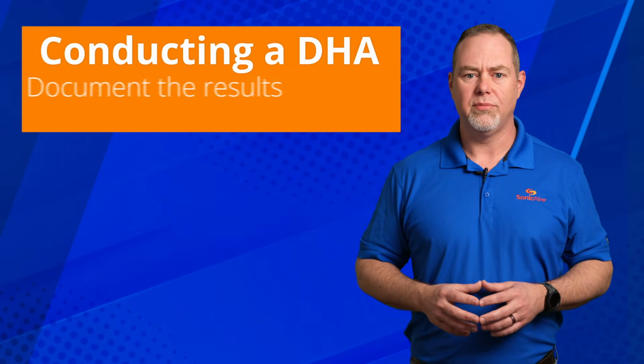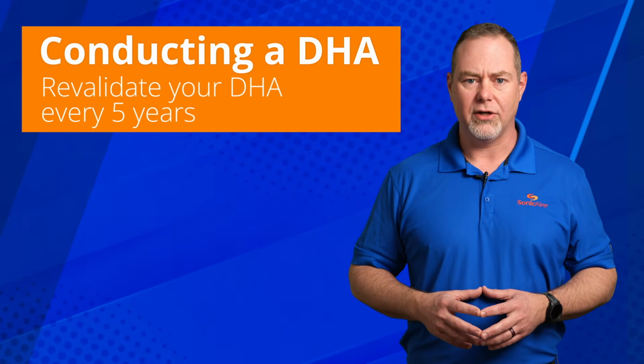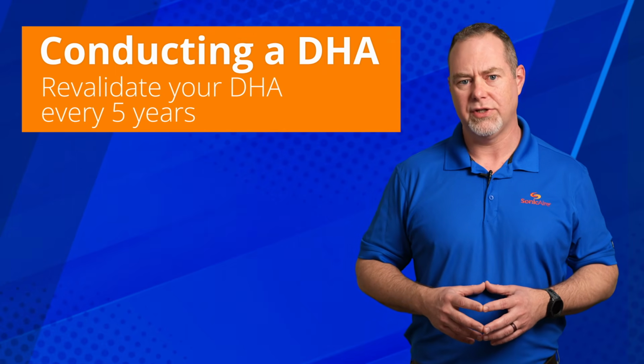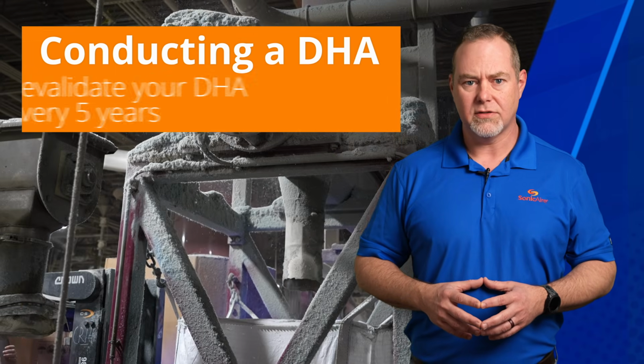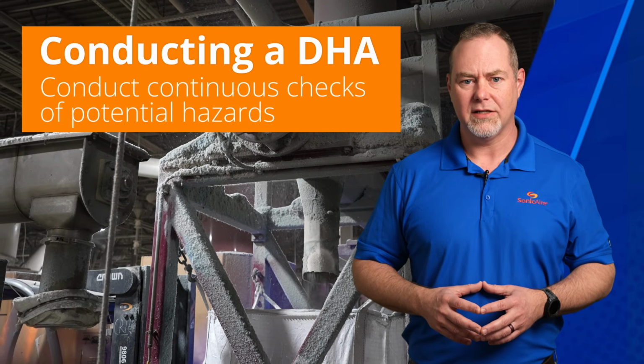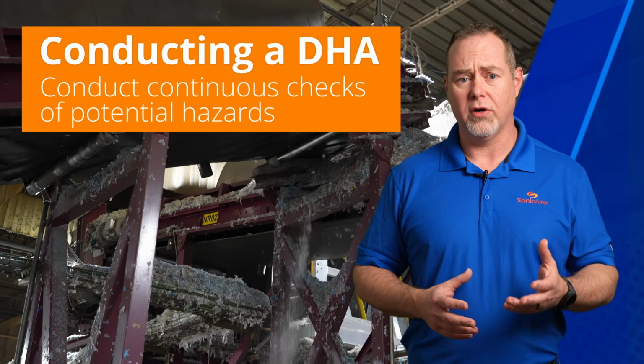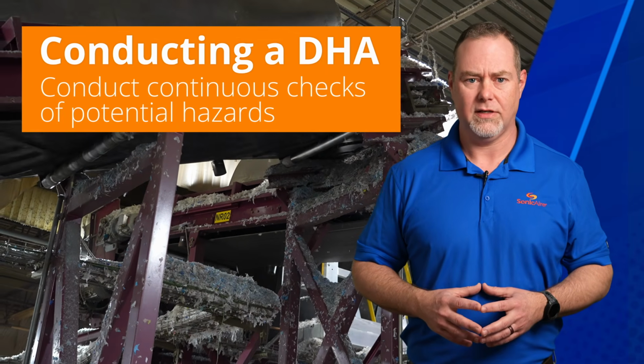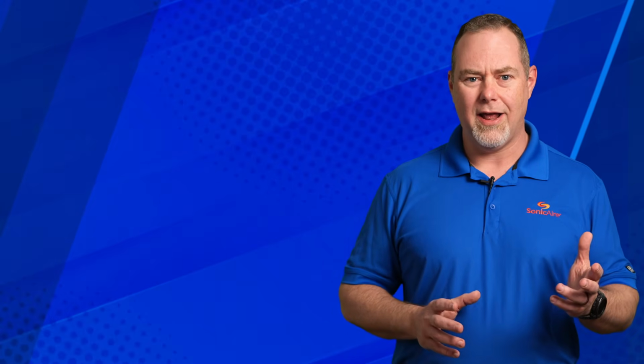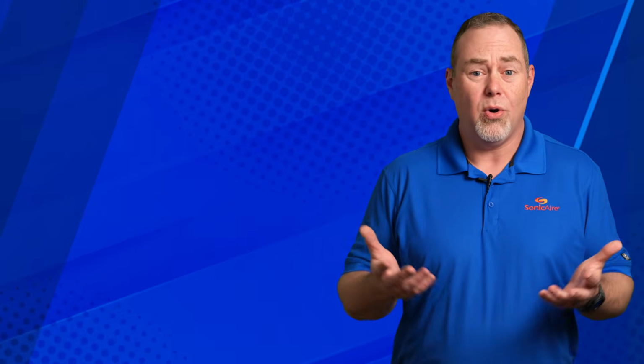Your DHA should be revalidated every 5 years or any time a process change is made. Processes or equipment that are identified as potential hazards should undergo continuous checks, usually as part of your preventive maintenance process. So we've defined the what and the how of a DHA, but why?